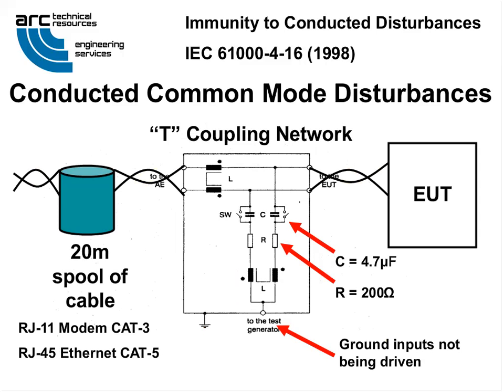My concern here about Ethernet would be that, as we've seen before, this is one pair. I'll put 4 of these in series with the Ethernet line, and I can almost guarantee the Ethernet line will stop working. So what you may end up having to do is survivability testing. If you find that you put this network in series with your Ethernet cable, and it does not talk, and it used to talk, you continue to deliver the energy as you were going to, but you'll have to check to see if the front end's okay afterwards.